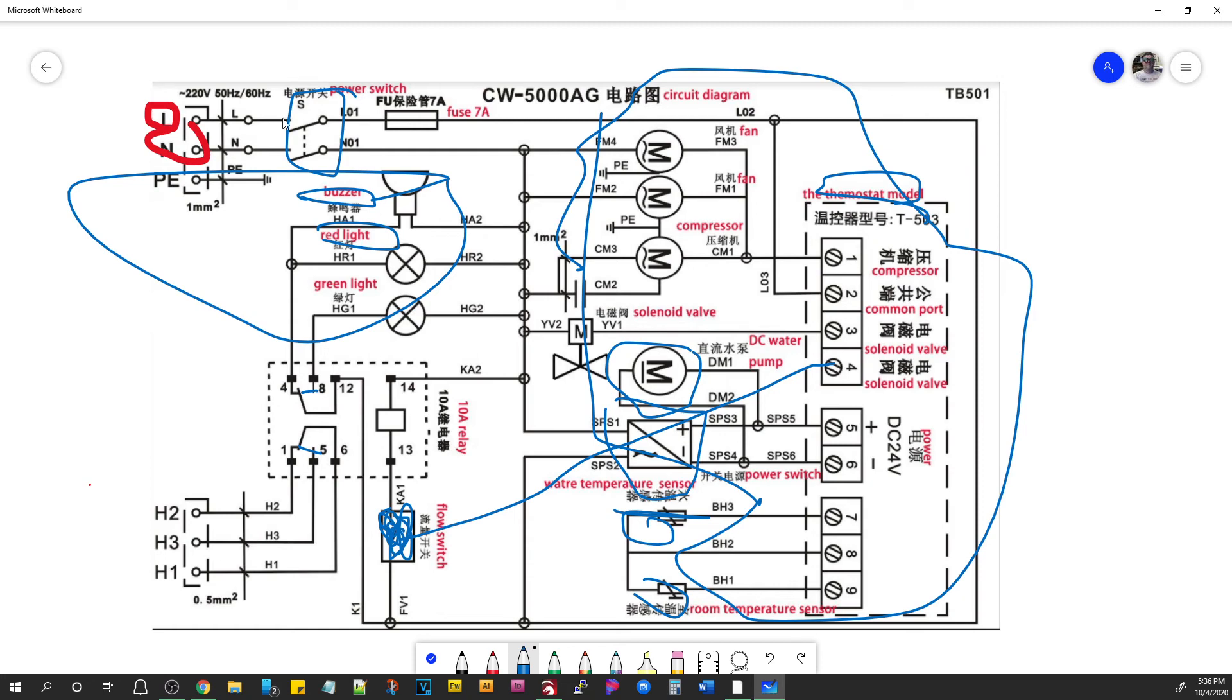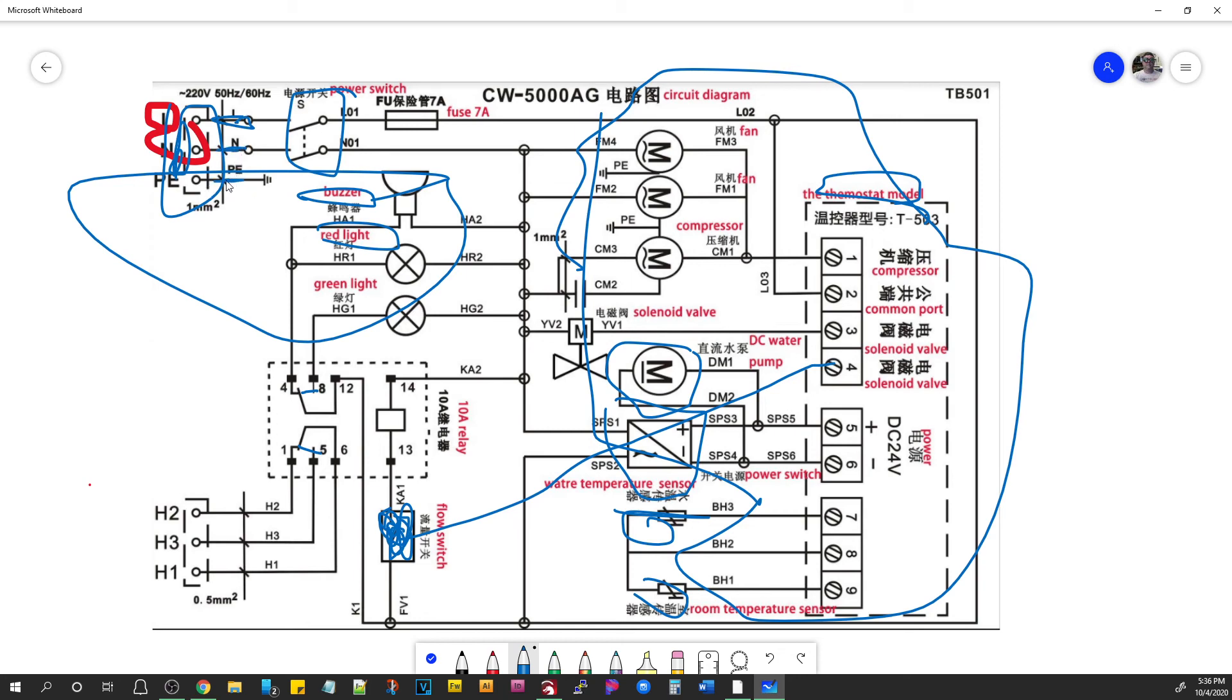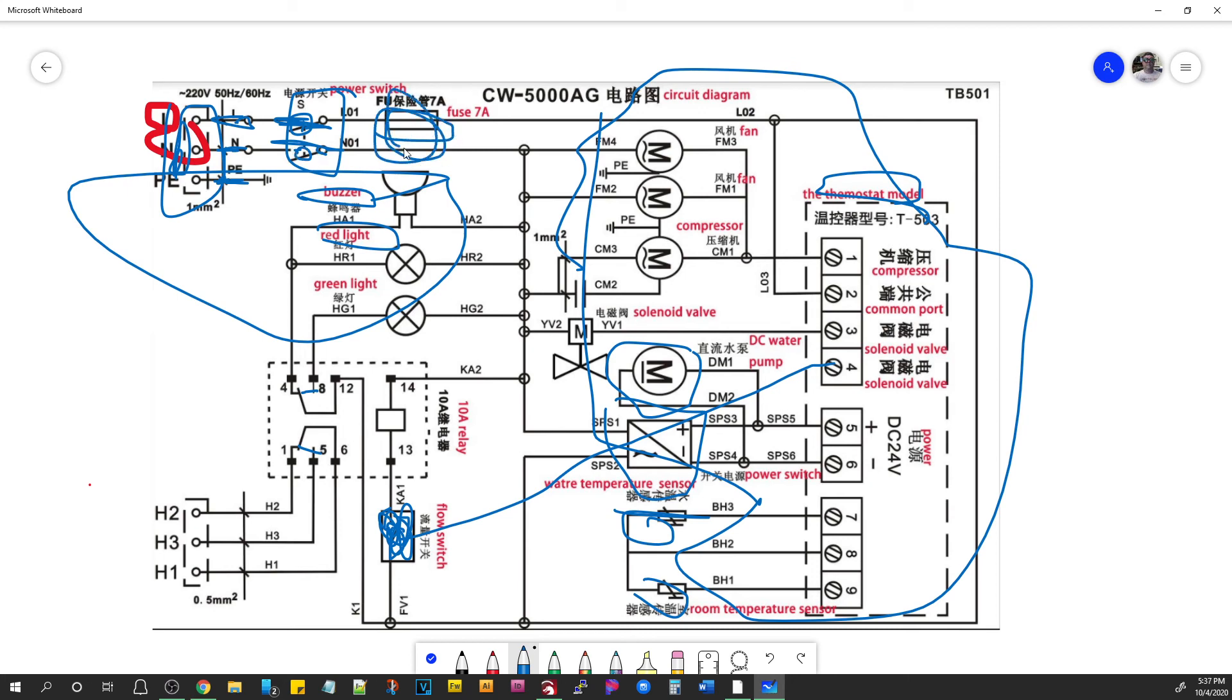So things to look for again are check the connections here. Make sure that the terminals are not corroded or arced, look like they've been arcing, or the plastic around them looks like it's malformed or has been heated. Check the terminals on the inside of the laser going to the connection for the chiller inside the chassis and make sure that all those terminations are good. The power switch can fail only on one side and not the other. And you can toggle that switch and sometimes it won't show any evidence that it doesn't work other than you've got a problem somewhere. Of course, numero uno, let me go back to the red pin, is going to be that fuse right there. Definitely check your fuse first thing.